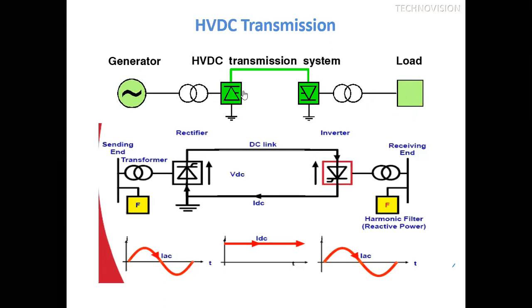Here, if you take this side, this is the rectifier station which is connected with the AC system like a generator through the converter transformers. These are the converter transformers. Then there are the rectifiers which convert AC into DC. Then there is a DC line, over which that DC is transmitted over a certain distance. Then again at the inverter station, that DC is converted into AC and fed to the load. So this is the system.